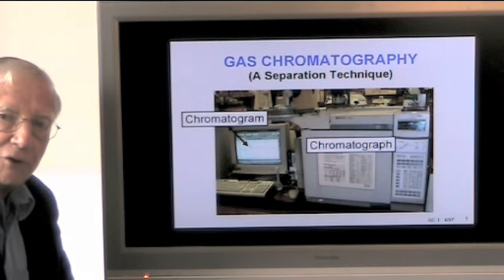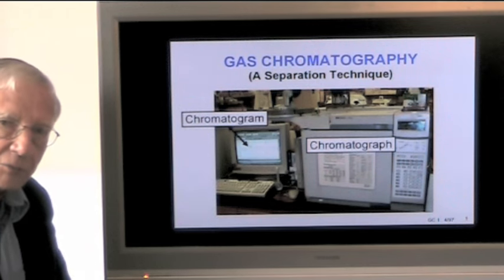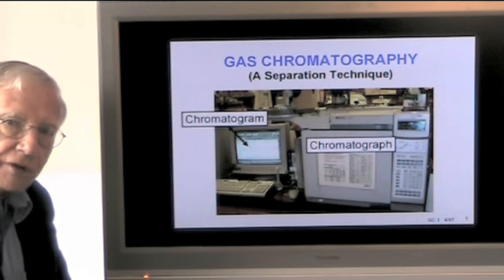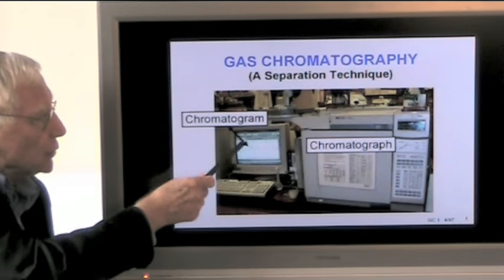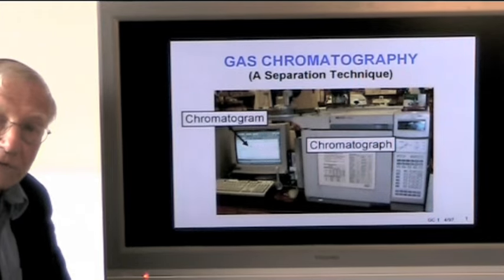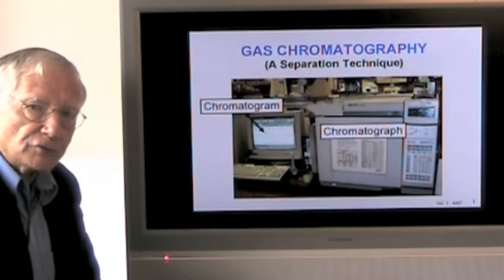This machine, by using an injection port, a column detector, generates a written record of the analysis, a series of peaks. And those series of peaks are called a chromatogram. A chromatogram is simply a written record of the analysis performed by the gas chromatograph.